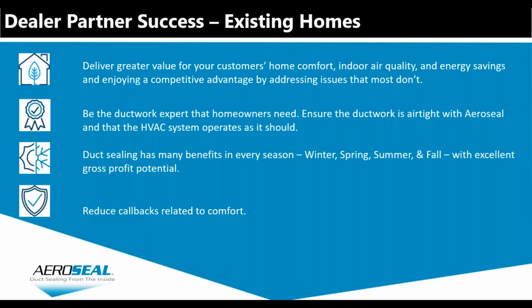The other thing here, the third: duct sealing has many benefits in every season. So this means that in winter, spring, summer, and fall, there's excellent gross profit potential for the contractors. This can be leading with system installs. So it's a great time to talk about the inefficiency of ducts when you're in the home and replacing the equipment. But on service calls, it's equally important, because what you can do is add airflow as a check on the service checklist, if it's not already on there.